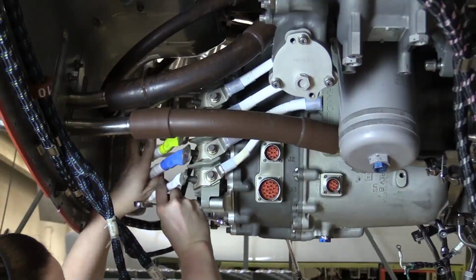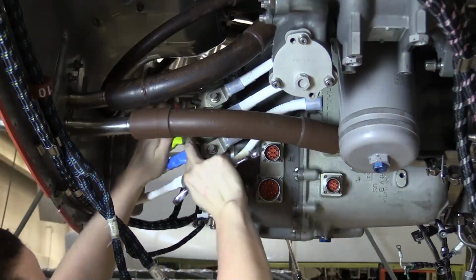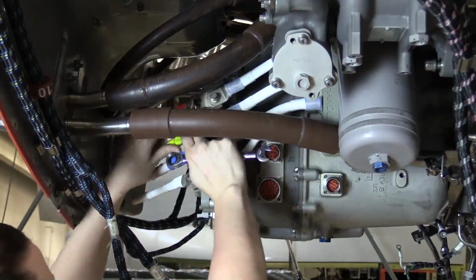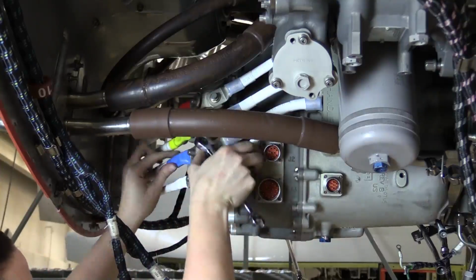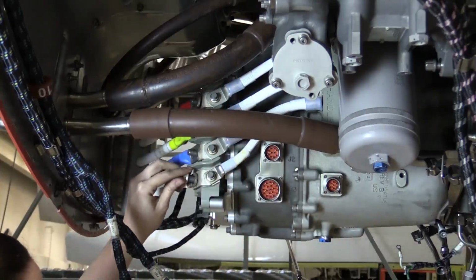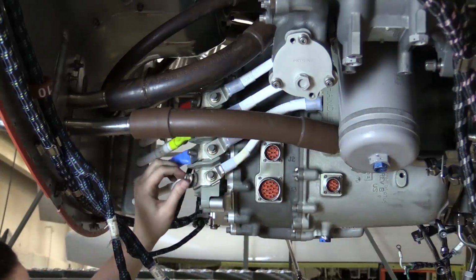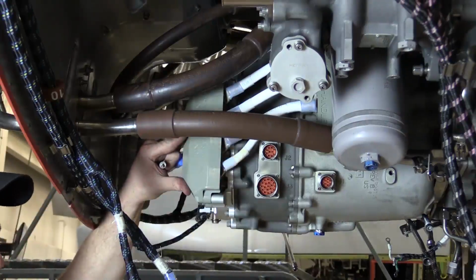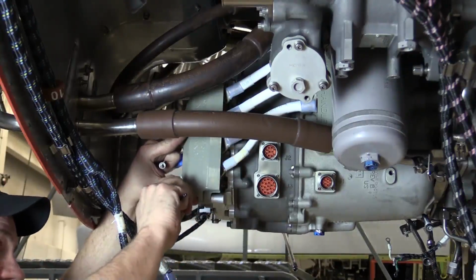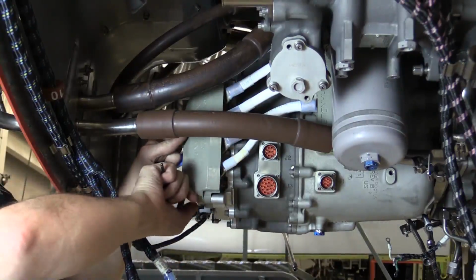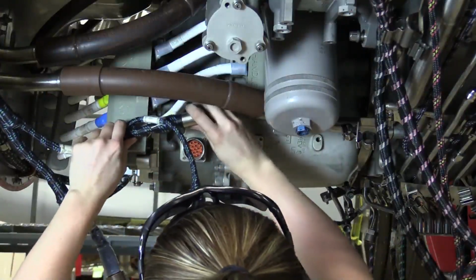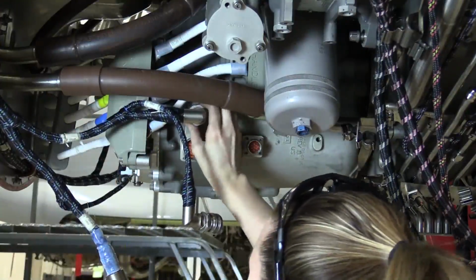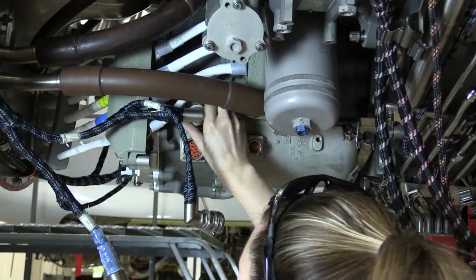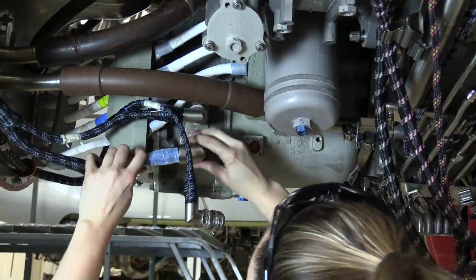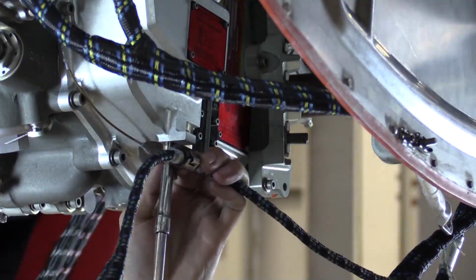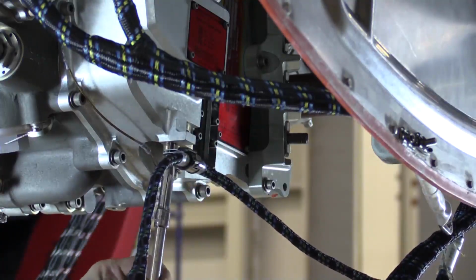Connect the power feeder cables and neutral onto the 4 terminal studs with the washers and nuts. Tighten and torque the nuts. Put the terminal block cover onto the variable frequency starter generator and install the washers and screws. Connect and tighten all the electrical connectors to the variable frequency starter generator. Install the bolt and clamp that attaches the wire harness to the variable frequency starter generator.